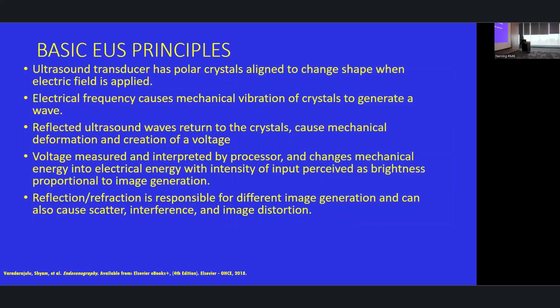So it's essentially sound that's getting interpreted into electrical energy, and the processor can then be used to make an image out of that. The take-home point is that transducers generate and receive acoustic signals via polarized crystals in the ceramic tip of a probe. These crystals deform based on sound wave reception, and the processor can control how loud the sound wave is, what hertz we're using, and things like gain and image intensity.